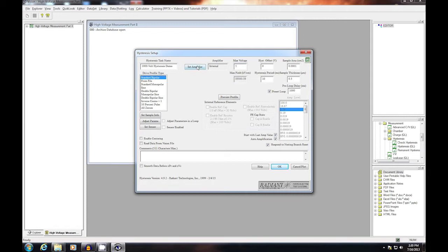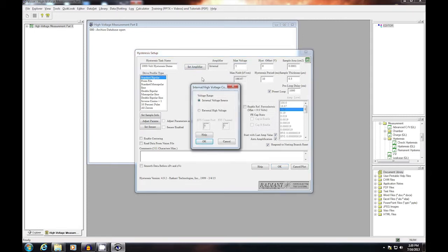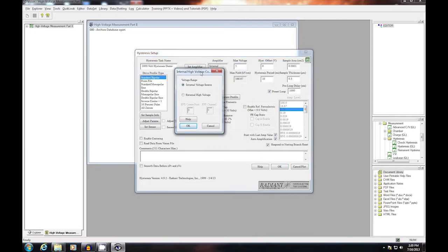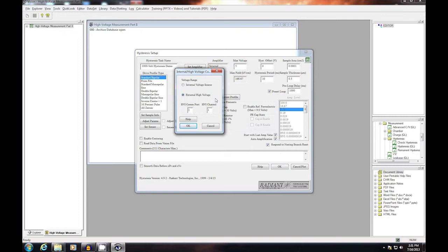And then go to Set Amplifier button, opening the Set Amplifier sub-dialog. I'm going to select External High Voltage. The HVI COM port is always set to 1. The HVI channel, however, reflects the selected channel of the amplifier attached to the HVI. If you have a single channel HVI, this value will always be 1. If you have a two channel HVI, such as I demonstrated in video 1, this channel setting will either be 1 or 2, depending on which of the two amplifiers you're selecting in software.